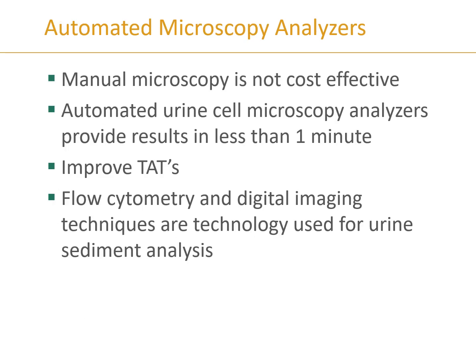One of the newer developments in laboratories is automated analyzers that perform automated microscopy. The technology has been developed using the same principles as CBC analyzers for cellular morphology analysis. Manual microscopy is not cost-effective — it requires tech time, specialized training, and extra supplies such as urine tubes used as waste material, whereas with automated analyzers everything is contained within the system.